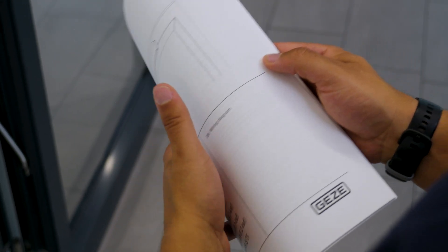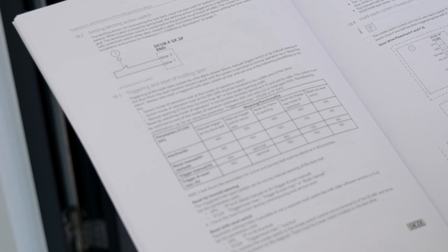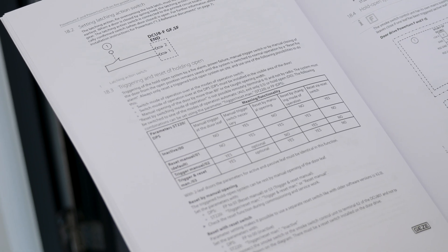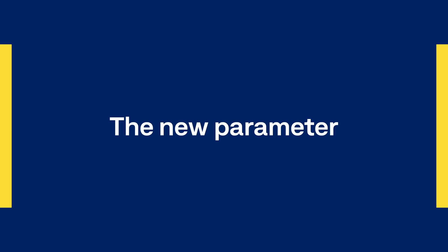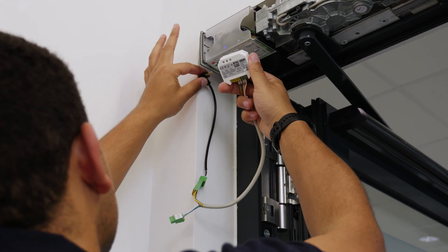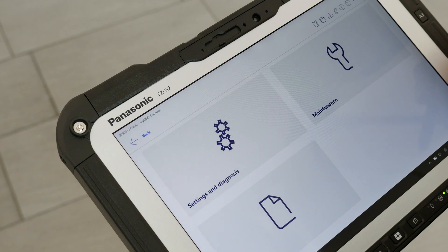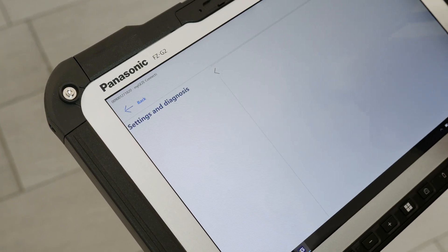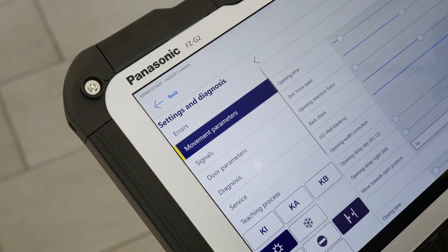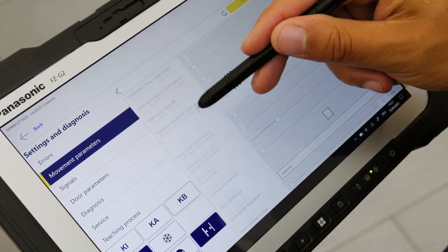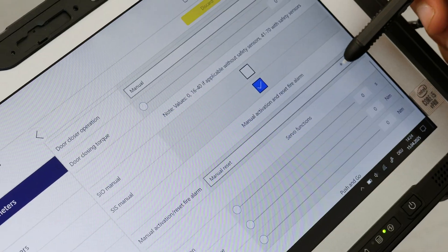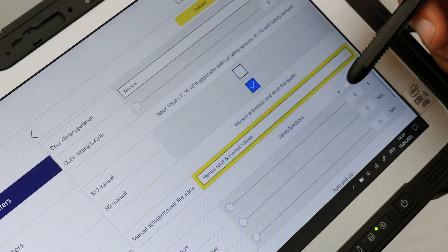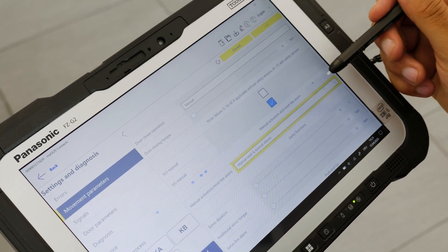There is a new parameter in connection with the new functions: manual release and reset of the hold-open system. Please refer to the wiring diagram for details. We will now show an overview using the commissioning app. You will find the parameter under Movement Parameters. The manual reset option is pre-selected at the factory. This means the hold-open system is reset by the movement of the door leaf and released by a manual trigger switch. If release via the door leaf should also be possible, you must adjust the parameter.